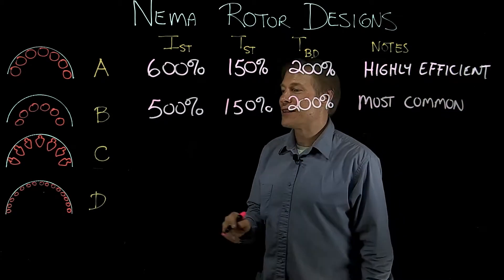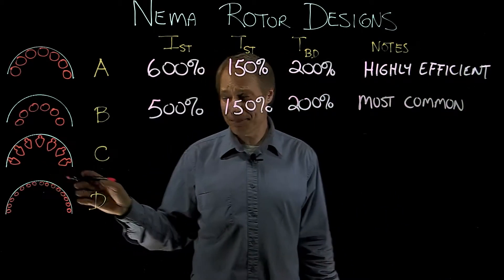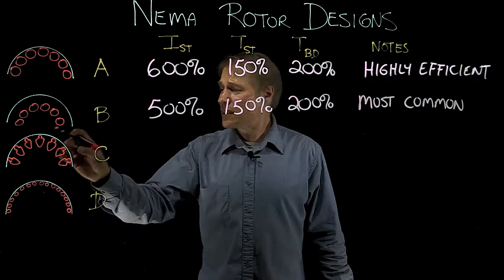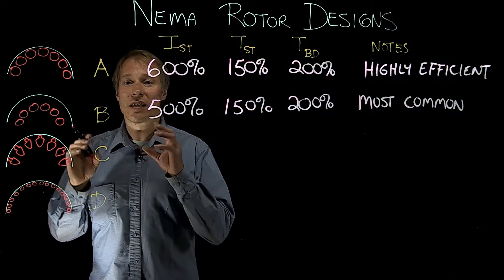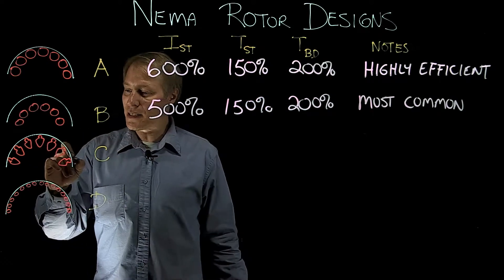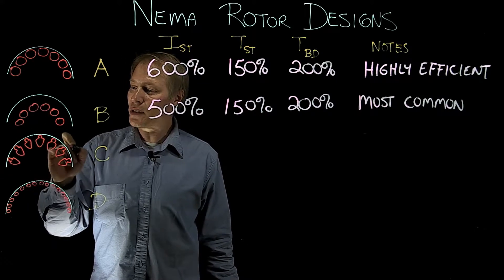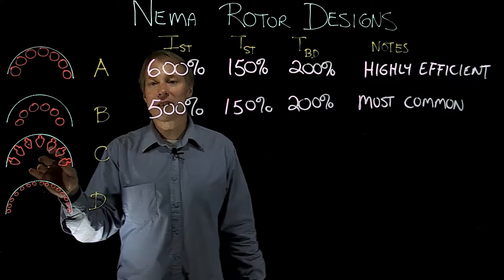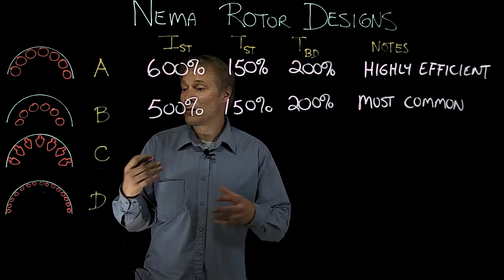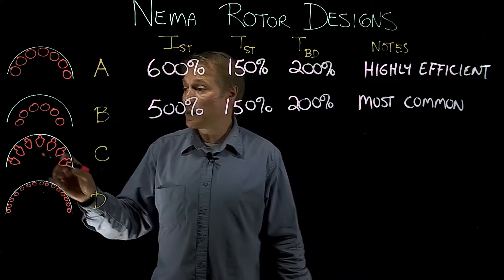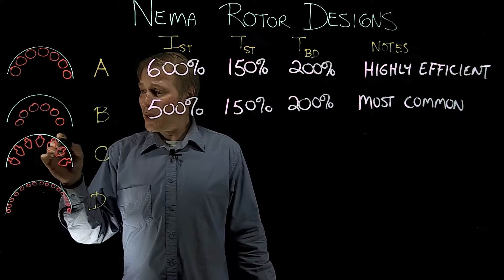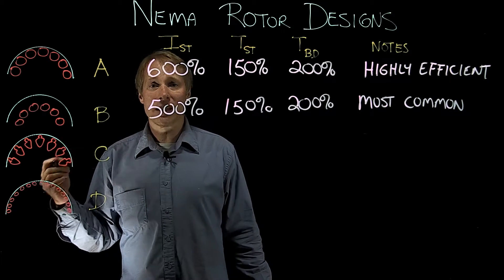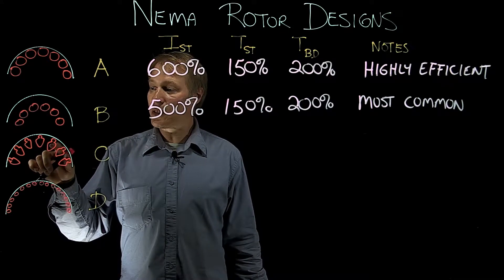Alright, moving on to the C design. Now the C design is quite special because it really has two sets. It has an outer set of rotor bars and then an inner set. In this case they're connected, but sometimes they're not, it just depends on the manufacturer. But what we have is called a double cage design, so we've got outer rotor bars and inner rotor bars.